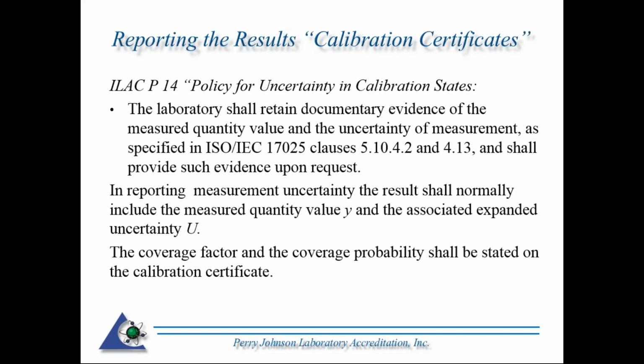Therefore, as stated in P14, we require that statement actually to be put on the certificate if the uncertainty is not being reported, that they are available upon request. So the laboratory should maintain all the necessary records which would back up the stated uncertainty, i.e. things like, let's say, temperature. If temperature was a component of uncertainty, the uncertainty associated with that contributor should be available.